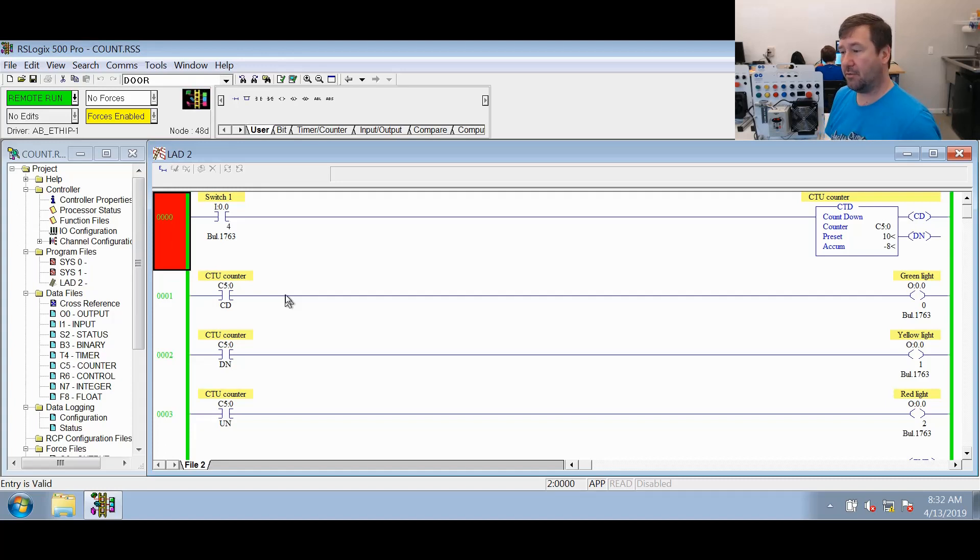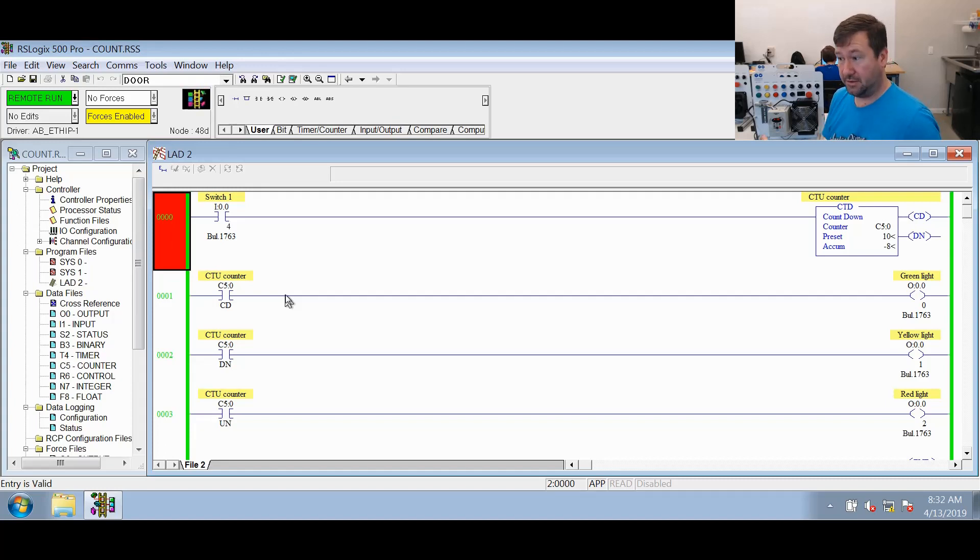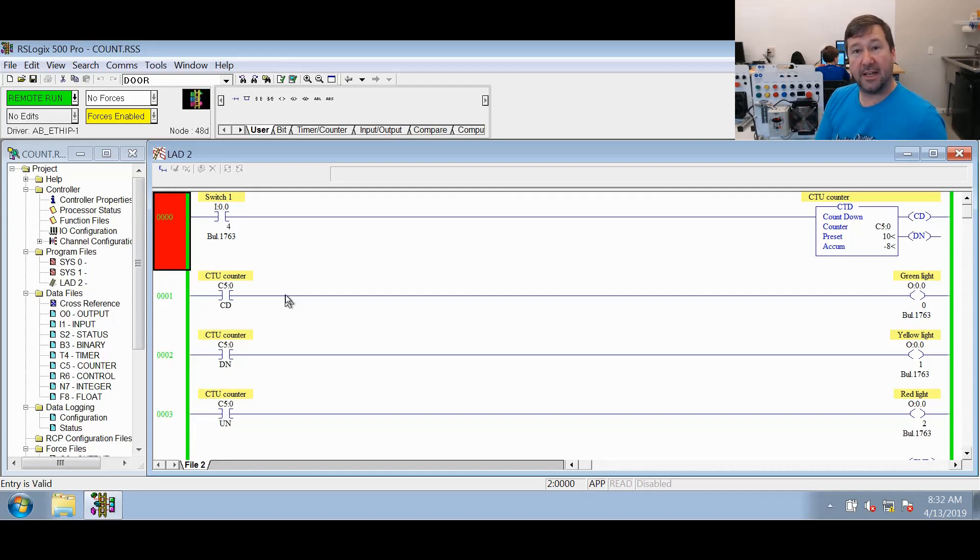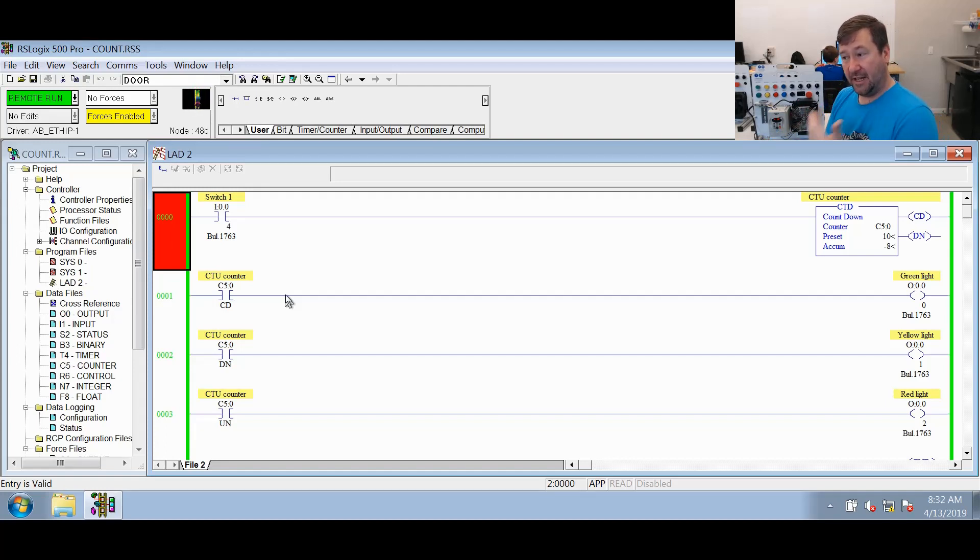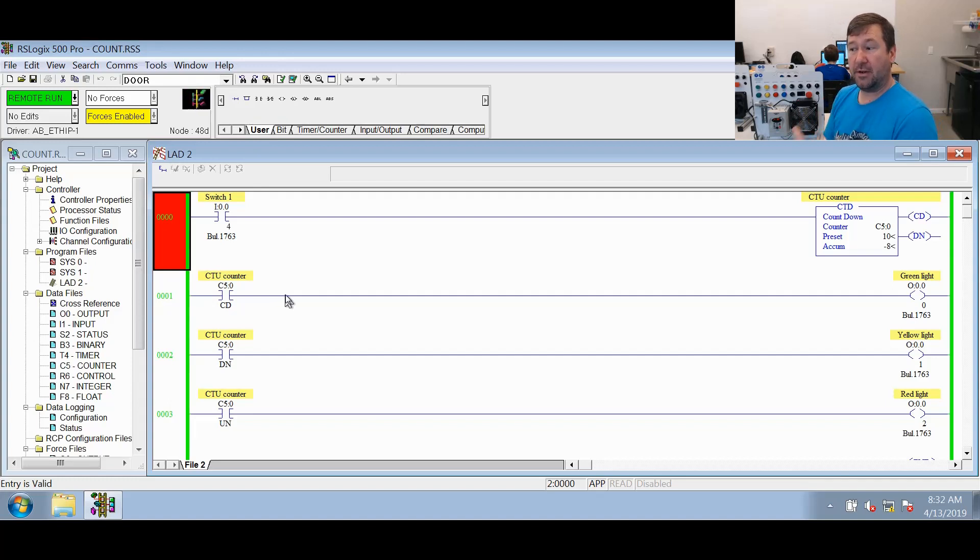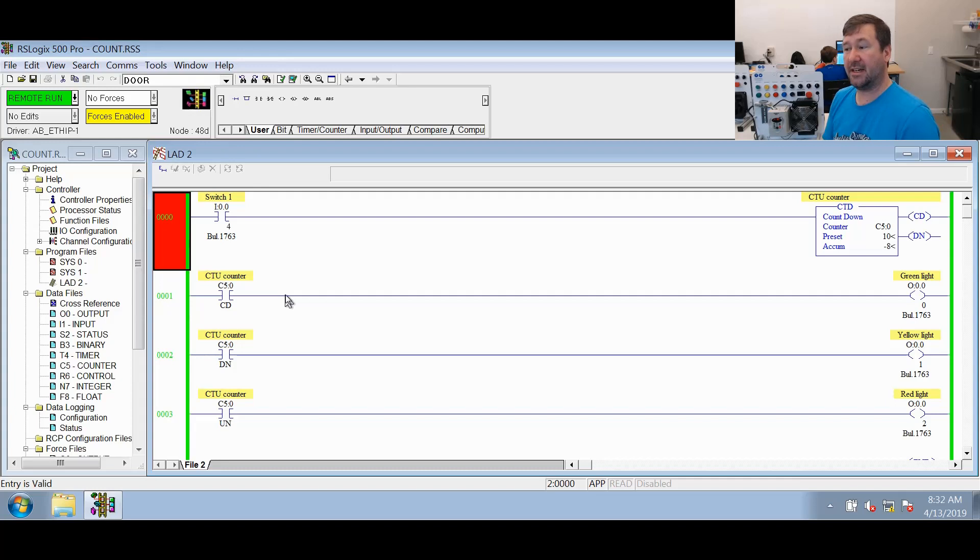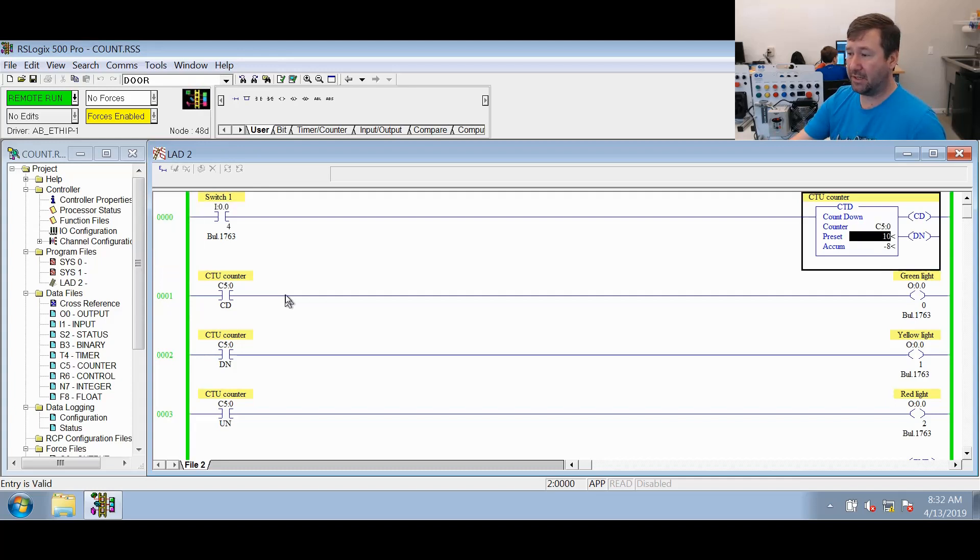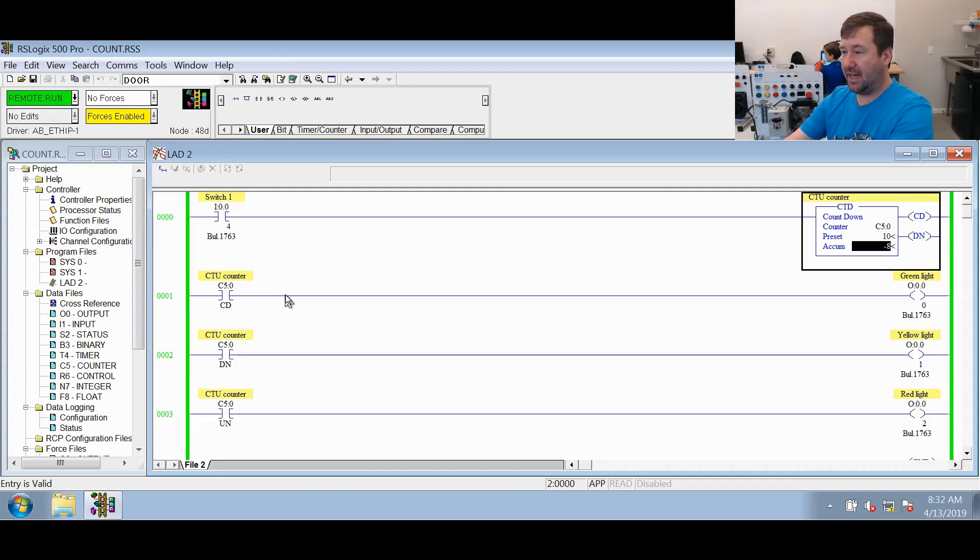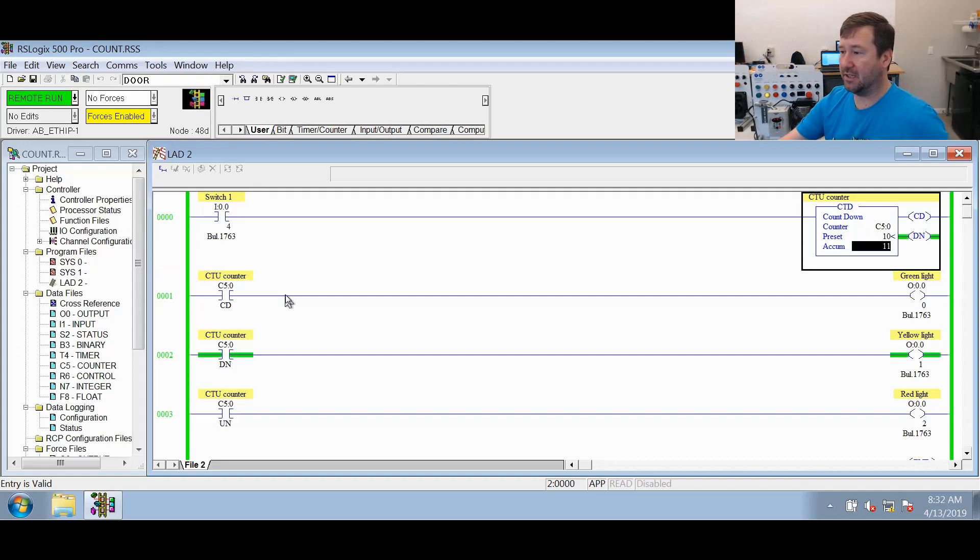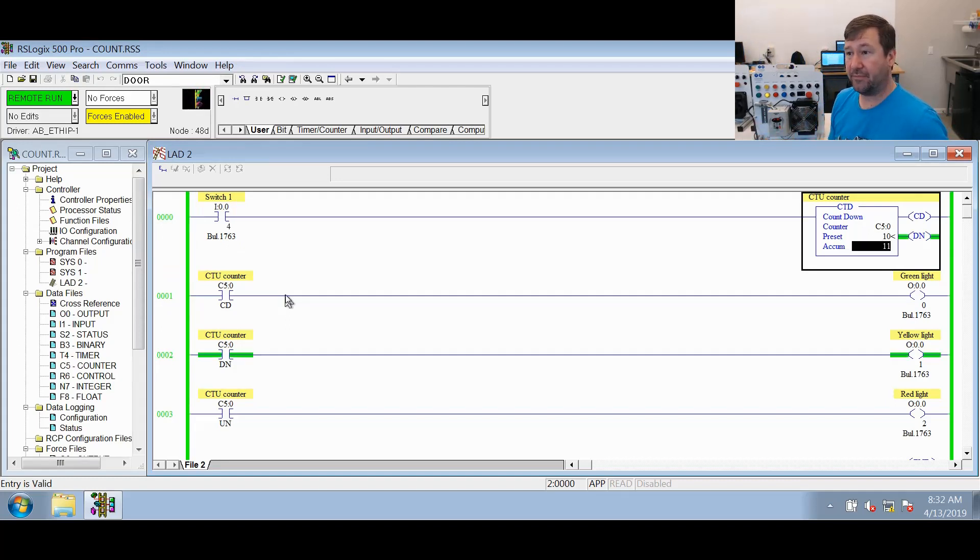So how do you ever get a countdown counter done? Well, it uses the exact same evaluation. If the accumulated value is greater than or equal to the preset or that OV bit is set, then it will be a one. So we can manually go here and select, let's just change the accumulated to an 11. You see our done bit is now a one.